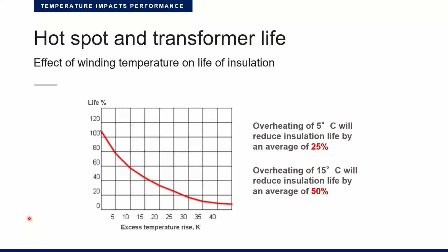And now looking at renewables, you can handle dynamic load. This is no problem. You can handle the unpredictable reverse power flow. You can overload your transformer as long as you control the temperature. And to control the temperature, you need to know the temperature. So knowing the temperature and controlling it is the key. That's why the temperature is so important today, more than it used to be many years back, when the transformers were in general loaded at 30-40%, and there was no huge dynamic load.